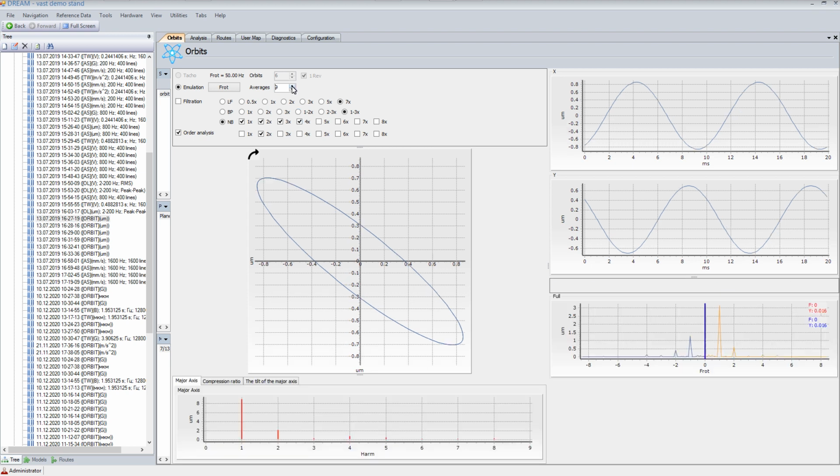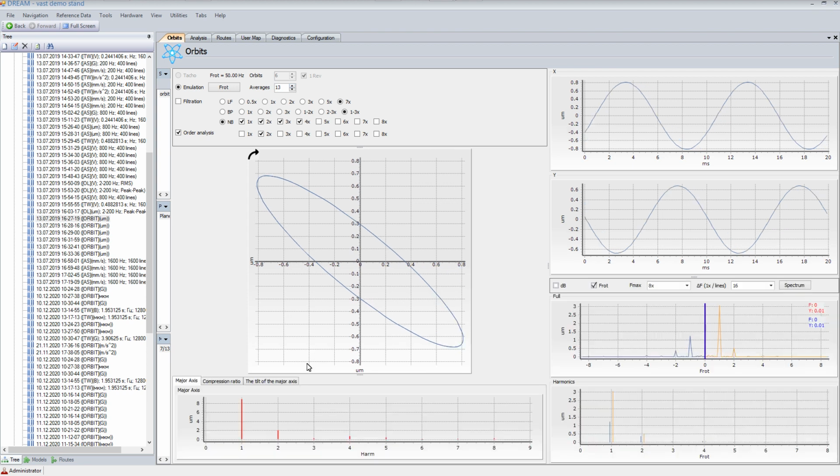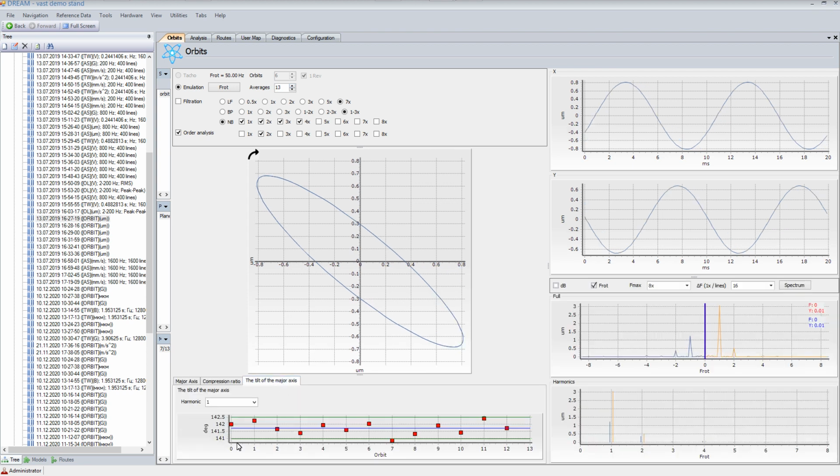The mean value is the blue, and these are each revolution or each spectrum that we can get. And the green ones are the deviation or root mean square error of these samples. So if you have some trend and your rotation evolves, then you will see it here.